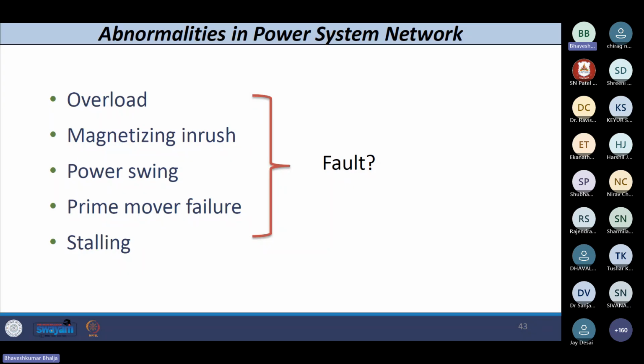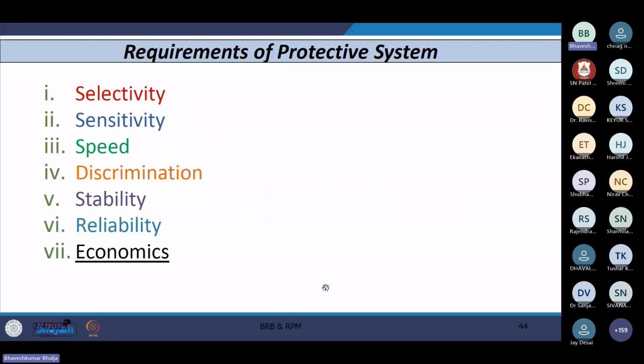And it depends on whether you have started the motor in hot condition or cold condition. Cold condition means you started the motor fresh, and hot condition means you started the motor, then stopped it, and after, let's say, 15-20 minutes, you restart it. So the temperature reaches its limit earlier than when you started the motor in cold condition. That is the difference anyway. Stalling is also not a fault, right? So that also needs to be discriminated from the fault situation.